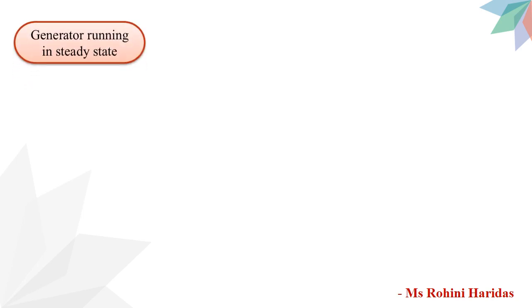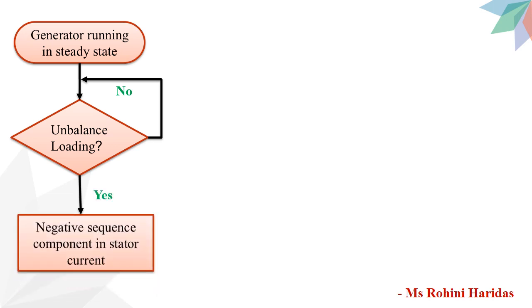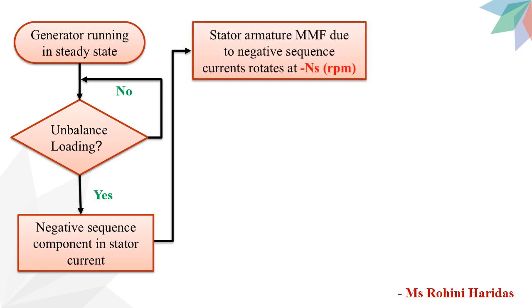Now let us see how unbalanced loading of the stator causes the rotor to overheat. Let us assume that the generator is running in a steady state condition. If there is an unbalanced loading of the generator, then the stator current will have a negative sequence component. This negative sequence component produces a rotating magnetic field which rotates at synchronous speed but in the opposite direction to the rotor speed.